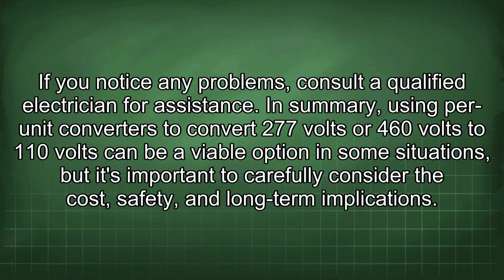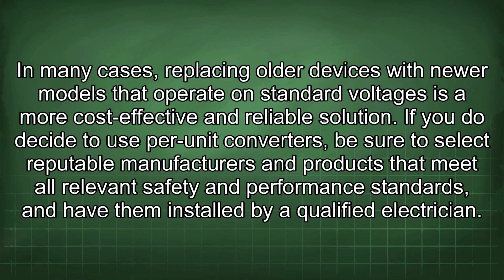In summary, using per-unit converters to convert 277 volts or 460 volts to 110 volts can be a viable option in some situations, but it's important to carefully consider the cost, safety, and long-term implications. In many cases, replacing older devices with newer models that operate on standard voltages is a more cost-effective and reliable solution. If you do decide to use per-unit converters, be sure to select reputable manufacturers and products that meet all relevant safety and performance standards and have them installed by a qualified electrician.